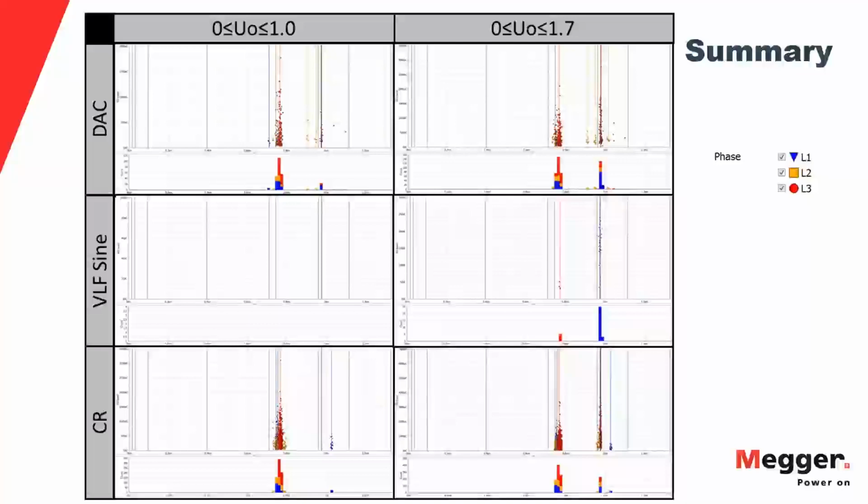And what was done was that these splices were opened up and problems were found and addressed, so to speak. So there was some repair work done. The PD activity that Jason showed you with the cosine rectangular in the cable insulation was in lead cable, like PILC cable, or let's say the European equivalent.